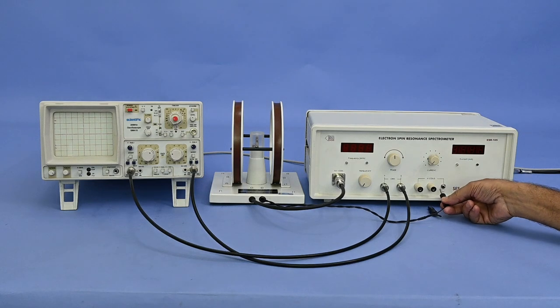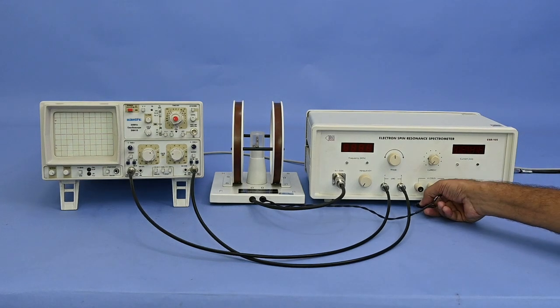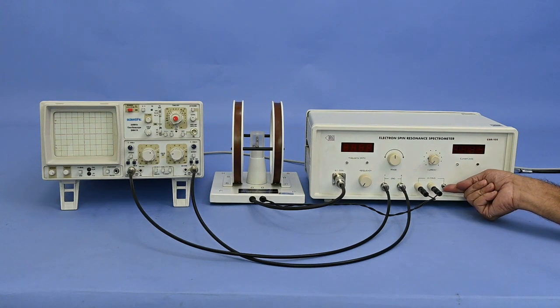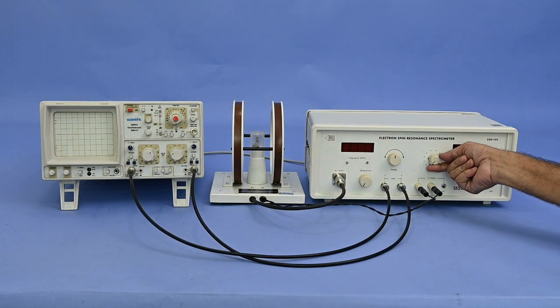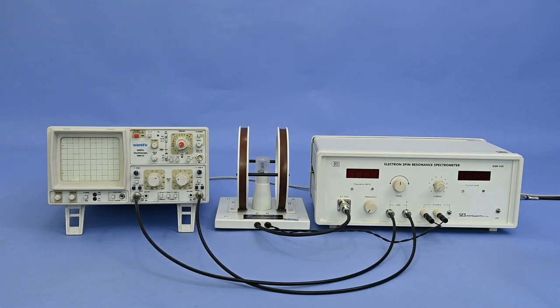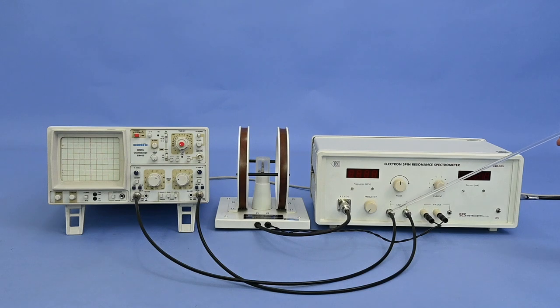Connect Helmholtz coil leads to H coil terminals with switch in OFF position and current at minimum step. Connect X and Y output signals of the ESR main unit to X and Y channels of the CRO.